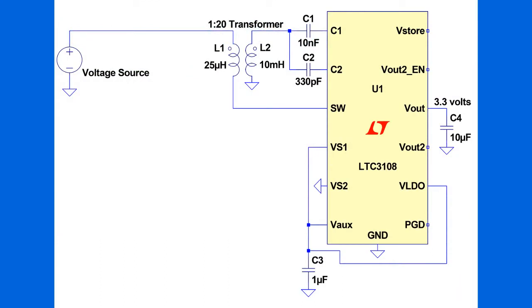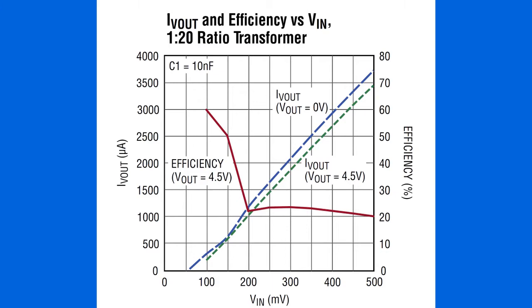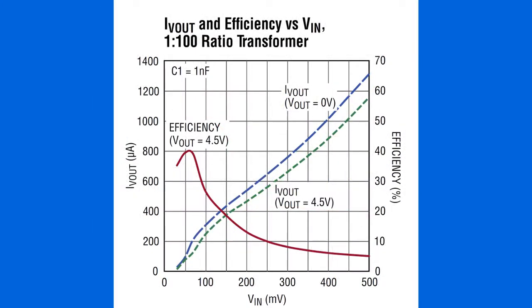This current setup requires an input voltage of at least 60 millivolts or so in order to operate, because it is using a 1:20 ratio transformer rather than a 1:100, which would operate down to 20 millivolts. However, a 1:20 ratio transformer is more efficient than a 1:100 ratio at a voltage above 100 millivolts, so we'll be using it instead.